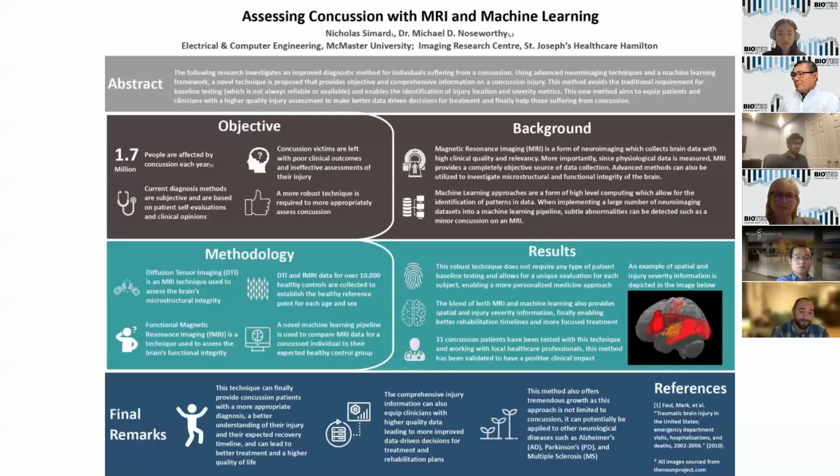But to also give you some hope for the future, there are new magnets at 0.5 Tesla that are being built. And when I say Tesla, it basically refers to magnet strength. A big issue with a 3 Tesla magnet, which is normally used in a clinic, is they're incredibly expensive. A 0.5 Tesla is much more affordable and can be used in trauma settings, and anyone can go into them. So that's actually one of the future ambitions of our research: we want to look into whether our big database can translate to these 0.5 Tesla systems to make them a lot more accessible for future use.